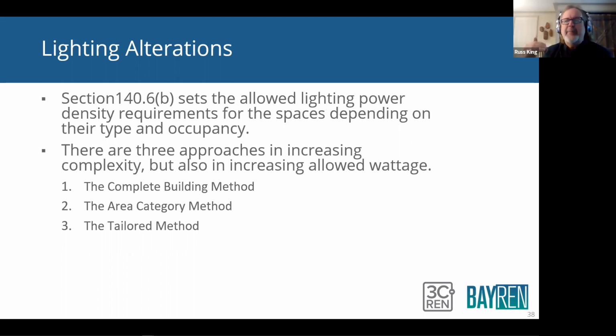And those three steps for determining your lighting power density are called the complete building method. That's the easiest one. That usually gives you the harder number to meet, or you can spend a little bit more time and do an area category method and get a number that's a little bit more flexible, a little higher number, it's a little easier to meet. Or you can go down to the, you know, specific, like I've got a jewelry case here.